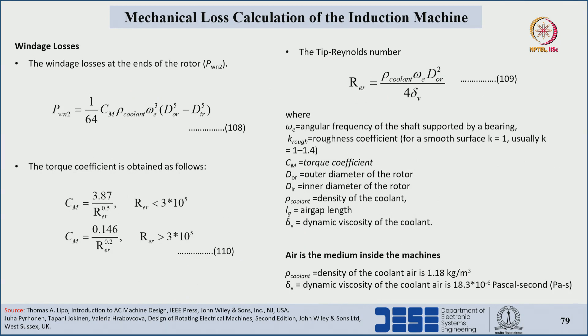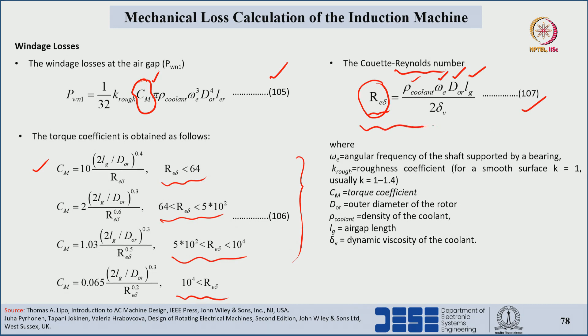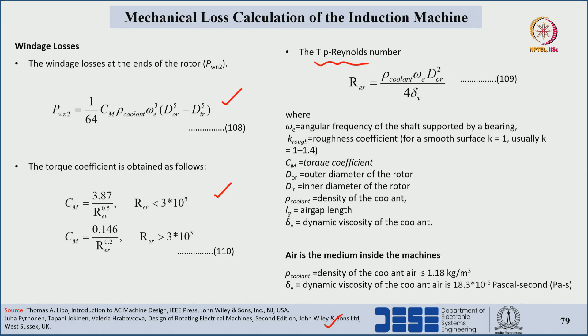Windage losses at the ends of the rotor are obtained with another formula based on assumptions and empirical relations, with partial proof in the reference. These losses depend upon the torque coefficient, which in turn depends upon the tip Reynolds number — a different variable from the Couette Reynolds number discussed earlier. The tip Reynolds number depends upon coolant density times angular frequency of the shaft times outer diameter of the rotor squared, divided by 4 times dynamic viscosity of the coolant.